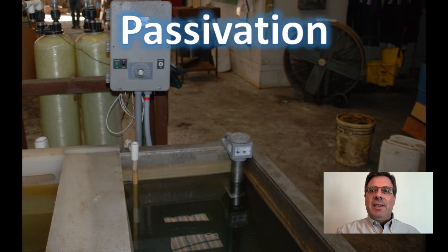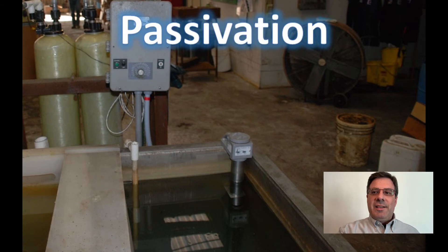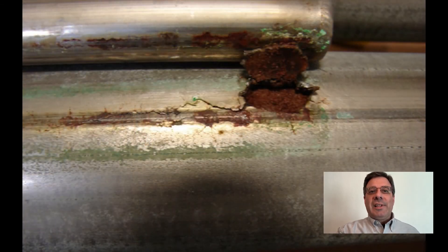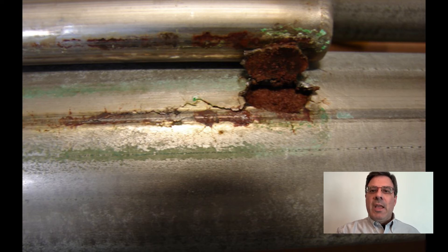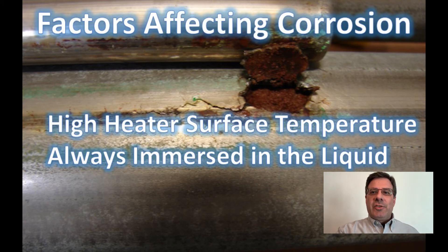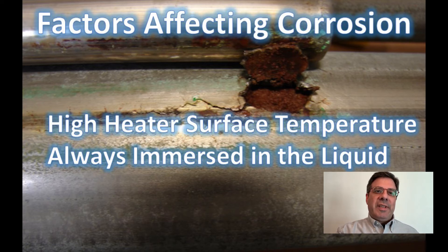Some customers may consider stainless steel heaters as suitable for a passivation tank because they expect the chemical will just passivate the metal. Also, the tank itself may be stainless steel. Unfortunately, there are a few key factors which can result in the passivation chemistry corroding the heater. First, when the heater is energized, the surface temperature of the heater is a lot hotter than the bulk liquid temperature. That higher temperature means there's more energy present on the surface of the heater, which could trigger or accelerate corrosion.